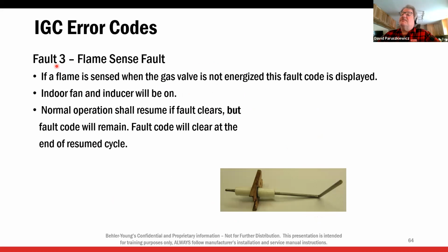All right, fault number 3, flame sensor fault. Now, a flame sensor, and we're going to talk about this in a second, is not a thermocouple. This is a piece of steel with a ceramic insulator. So a flame fault means that we sensed a flame when one shouldn't exist. That's probably a crack in the ceramic. A chunk of rust across it is not going to cause a faulty flame.